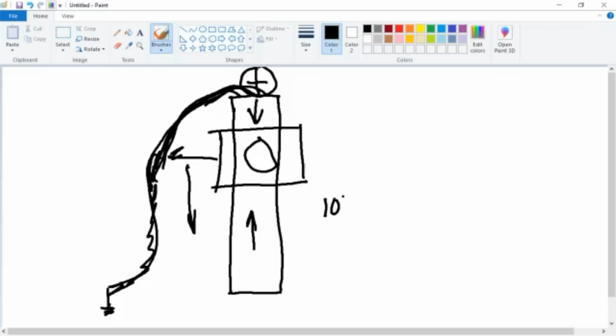If you have 1,000 amps going to ground from a fault and the 1,000 amps coming out of the elbow headed to ground, it won't do anything. It actually cancels itself out. And the fault indicator thinks everything's okay. So that doesn't work. So you have to use either one of the two methods that I've shown before.